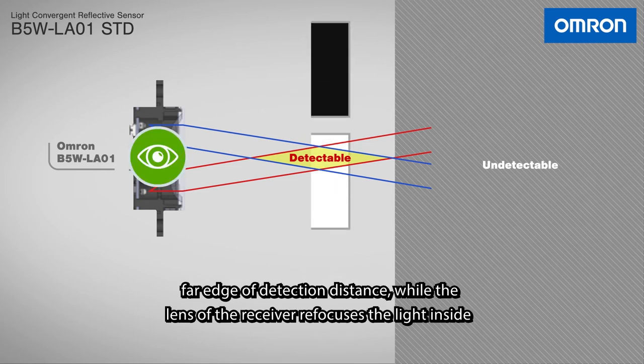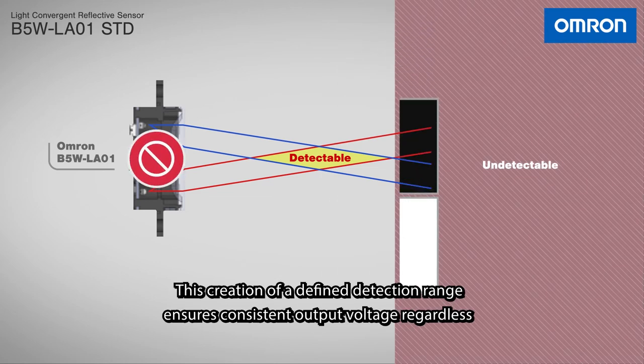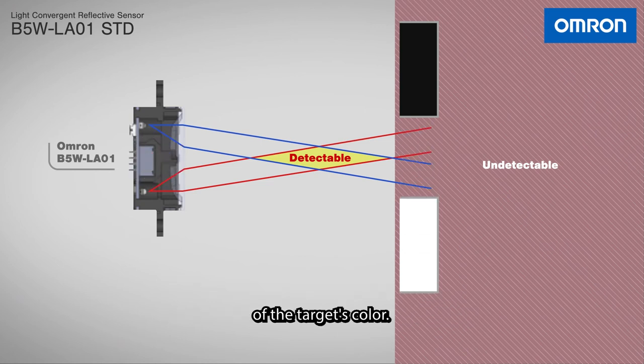The lens of the receiver refocuses the light inside of the convergent zone. This creation of a defined detection range ensures consistent output voltage regardless of the target's color.